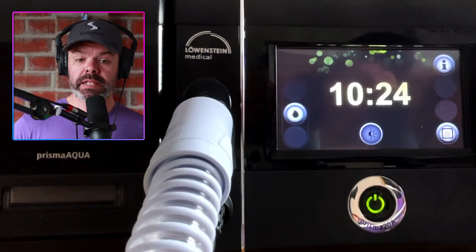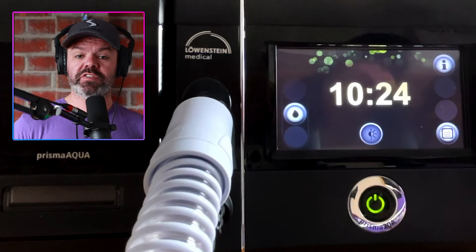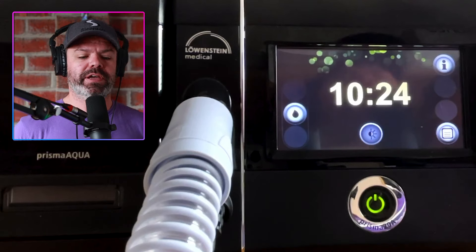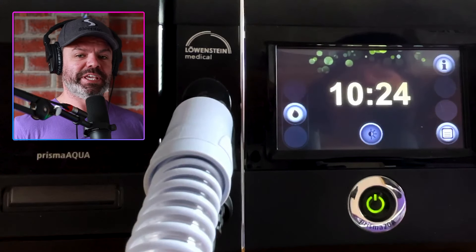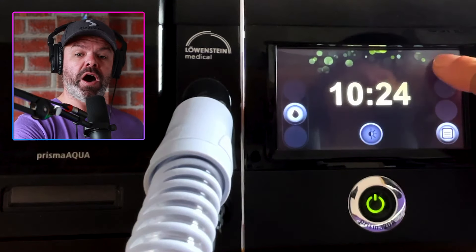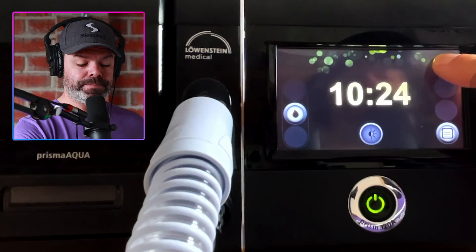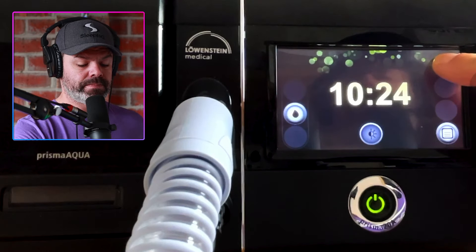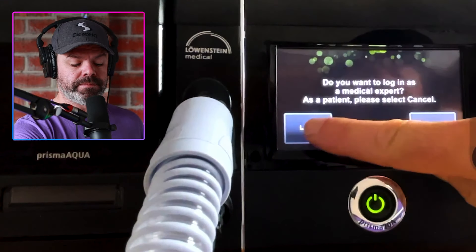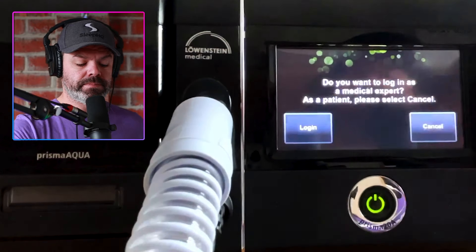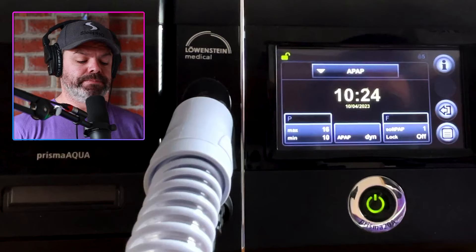Today I'll show you how to access the clinical menu where you can change advanced features like the therapy mode and pressure levels. To begin, click and hold the eye icon in the top right, then click login, and we're in — it's as easy as that.